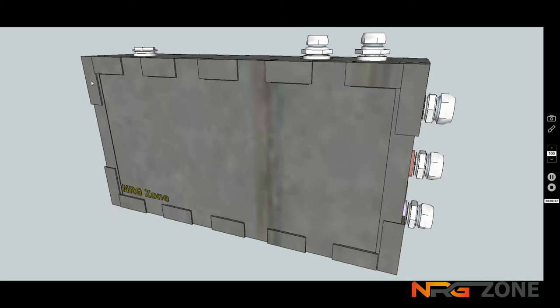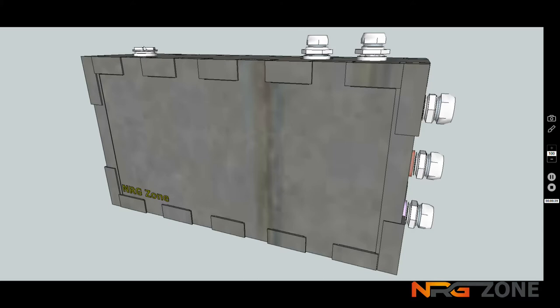You'll see there are three connections on the left-hand side as there are three connections on the right-hand side, defined as L1, L2, L3, and on the right R1, R2, R3. You have three connections on top. This would sometimes be used as an additional zone, or to introduce a thermostat, an overall system thermostat if necessary. In this situation, we're using this for an expansion and a cold feed, but it can also be used as a primary circuit to heat a cylinder if necessary, which is shown in a different video, with this being the return.